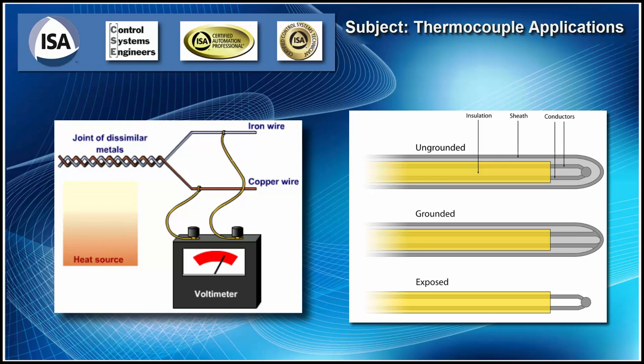And so they're showing this voltmeter connected to the thermocouple, but in reality, at room temperature, you'll never read anything. You have to add what's called a cold junction, and we'll talk about that in a minute. When we assemble these thermocouples, we put them together and typically put them inside a metal sheath to protect them.